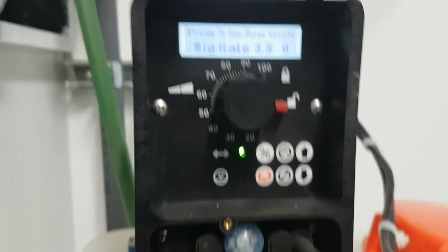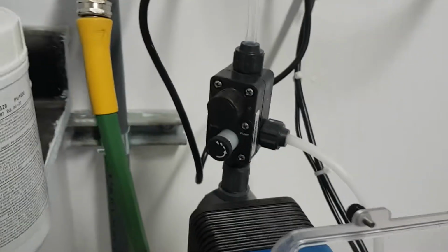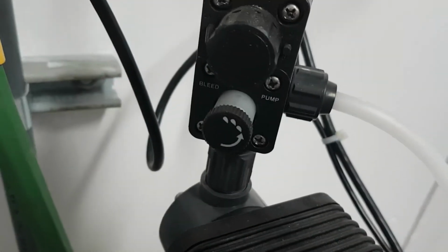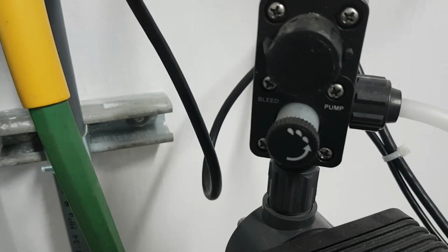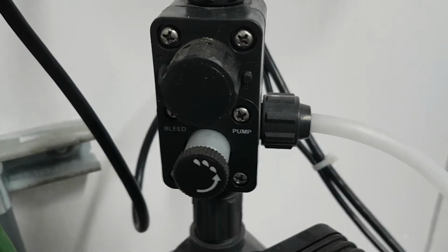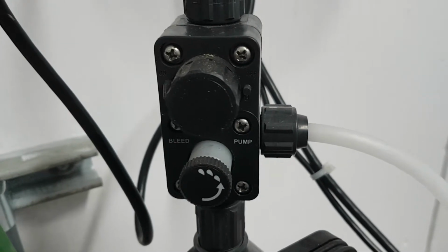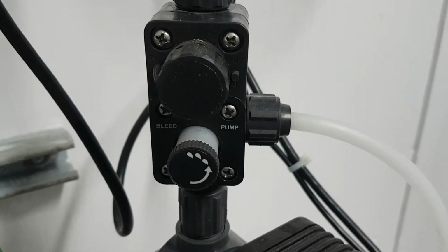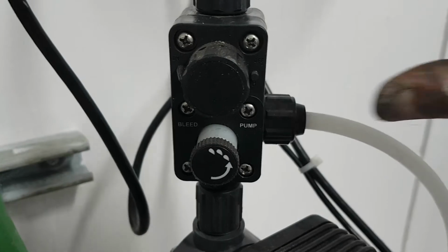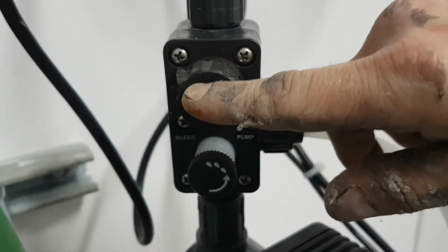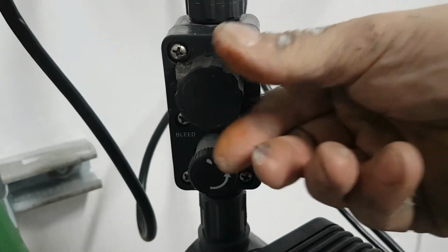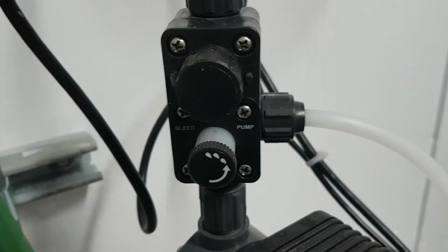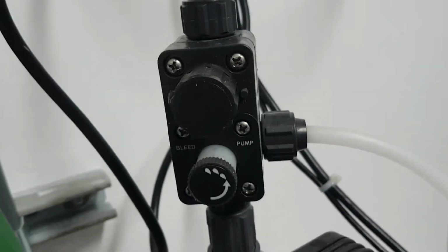The only other thing to show you with this pump is this 5-function degas valve. It has 2 knobs on it. The top knob is a back pressure, and it basically keeps a back pressure on the pump at all times so that if there's ever a vacuum in the line, it won't just suck the chlorine out of the barrel faster than you want. And so you should basically always have that in the on position, which is over on that side. You can see it if I move it here, there's a little pointer. I've got it pointing straight up now. That pointer should be over to the far left. So basically just leave that top knob to the far left.